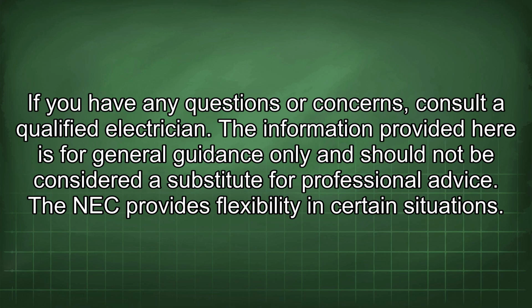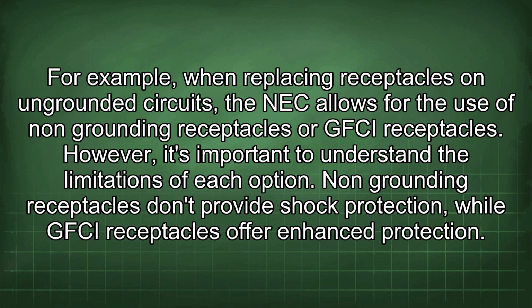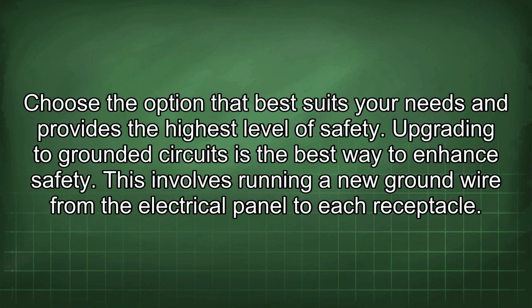The NEC provides flexibility in certain situations. For example, when replacing receptacles on ungrounded circuits, the NEC allows for the use of non-grounding receptacles or GFCI receptacles. However, it's important to understand the limitations of each option. Non-grounding receptacles don't provide shock protection, while GFCI receptacles offer enhanced protection. Choose the option that best suits your needs and provides the highest level of safety.